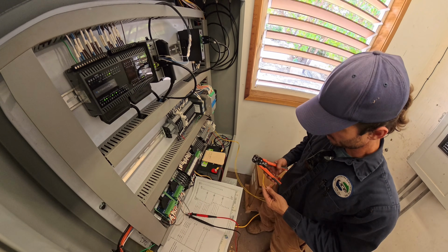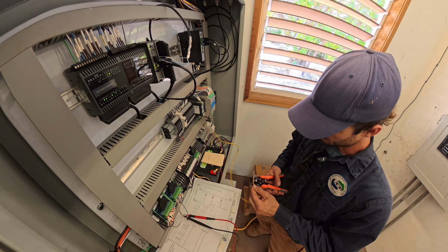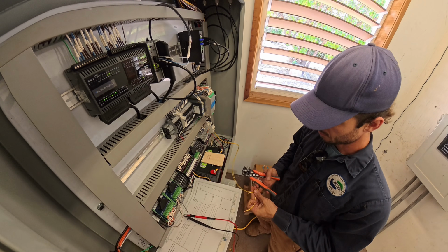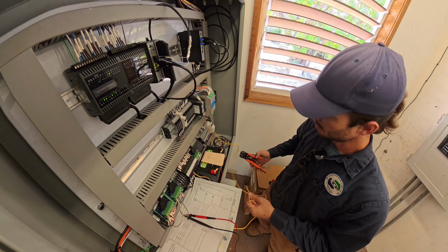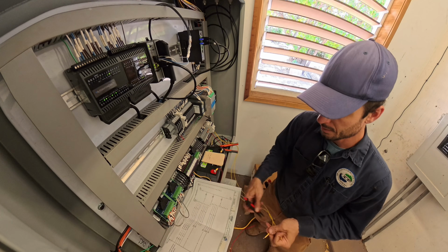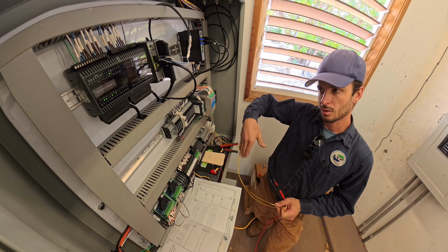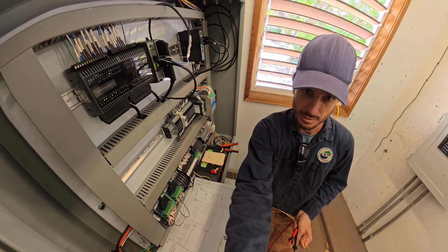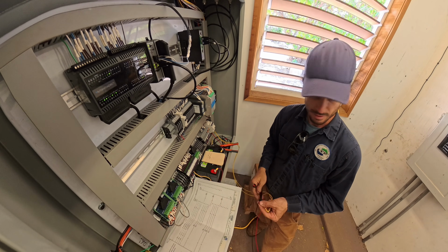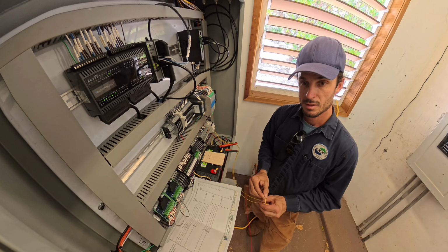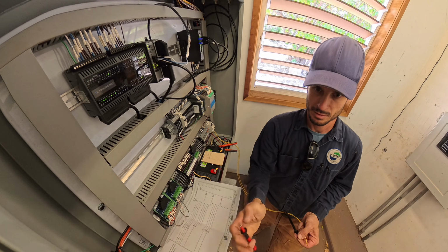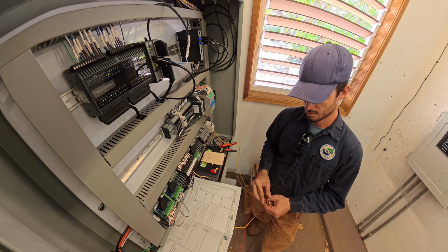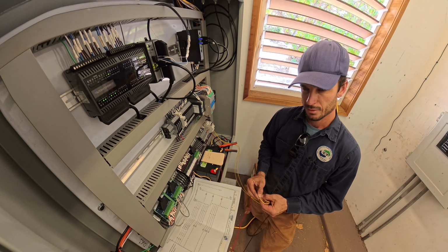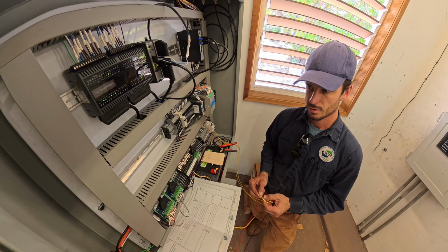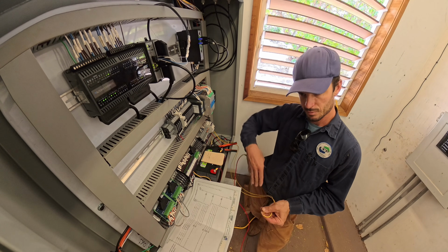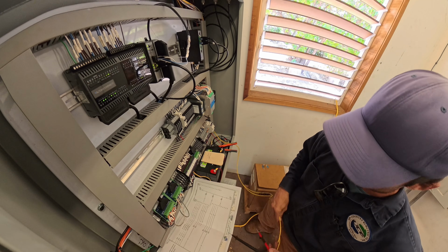Alright, so the first thing before I landed here, I'm just curious if this float switch is normally open or normally closed. I'm going to assume it's normally open. Normally open and closes when it rises. So let's see here though. Just a continuity check. I've already got it landed on the other end. Helps if the meter is on. There we go. So yeah, closed, so it would be normally open. Close on level change or state change.